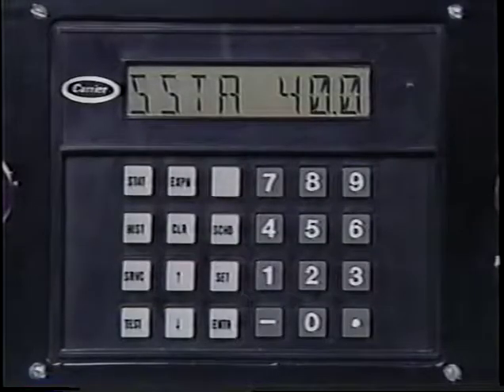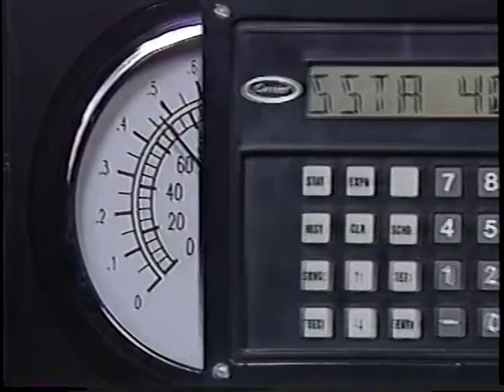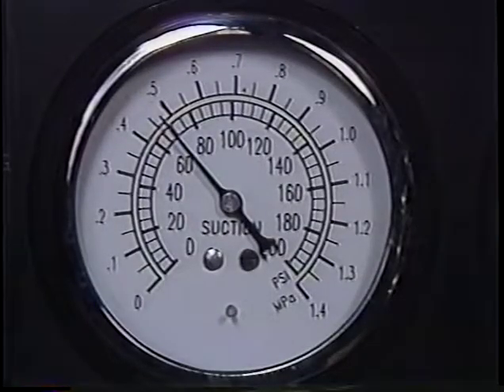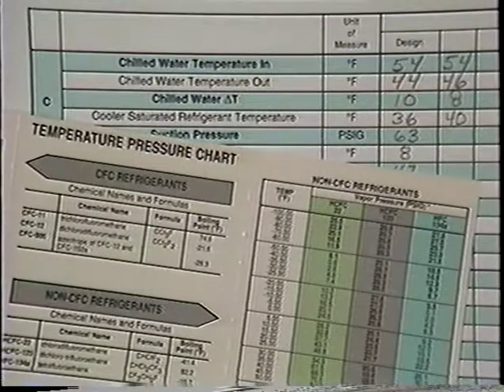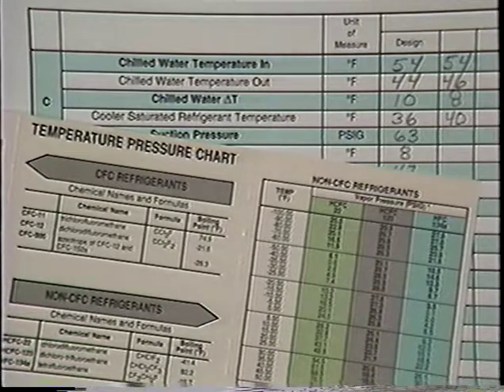If you cannot measure the actual cooler saturated refrigerant temperature, then the saturated temperature corresponding to the suction pressure may be used as the actual cooler refrigerant temperature. This temperature is required for determining the cooler leaving temperature difference.